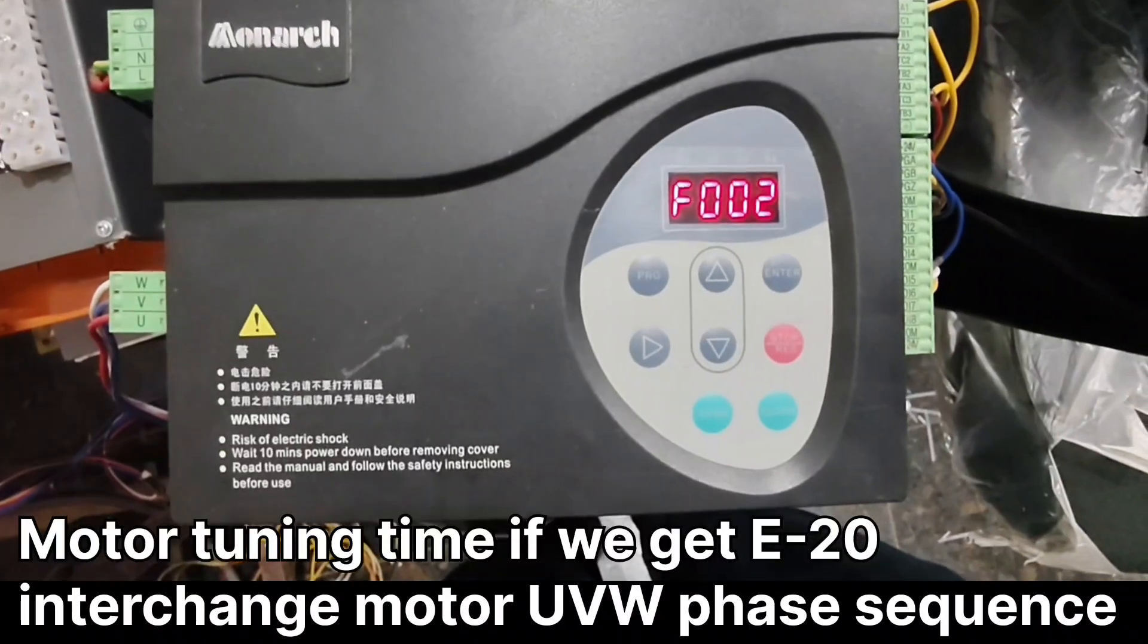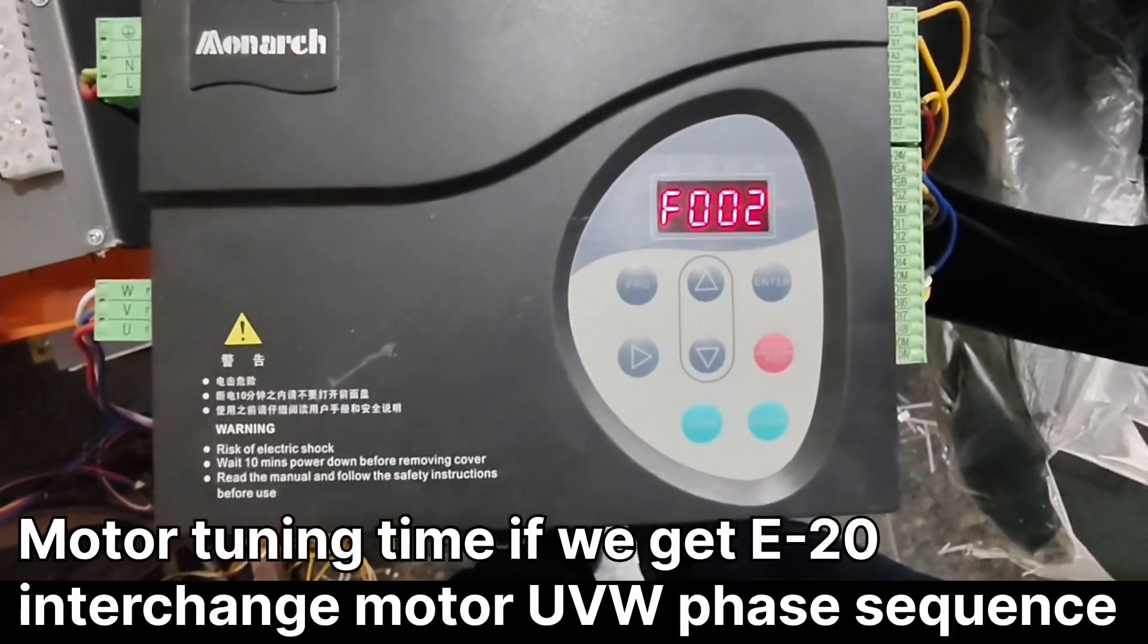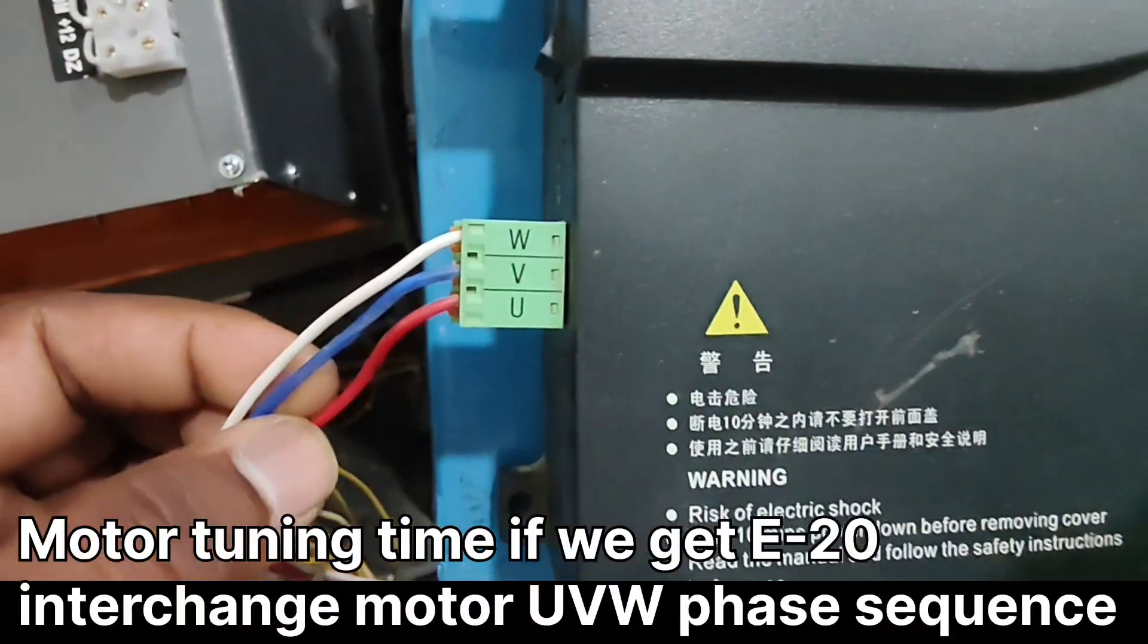In motor tuning time, if you get error 20, please interchange the motor UVW phase sequence.